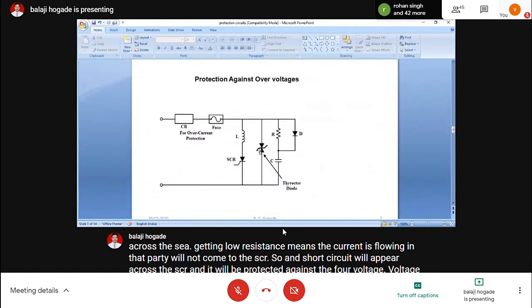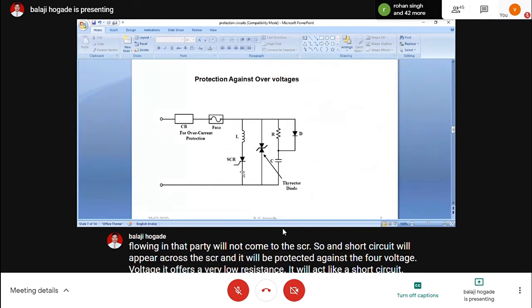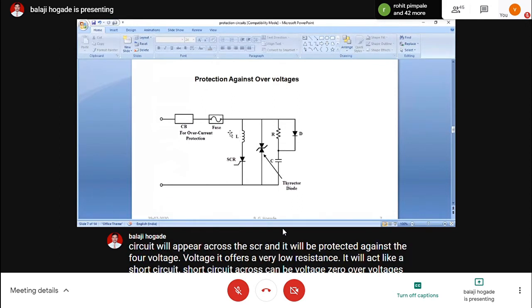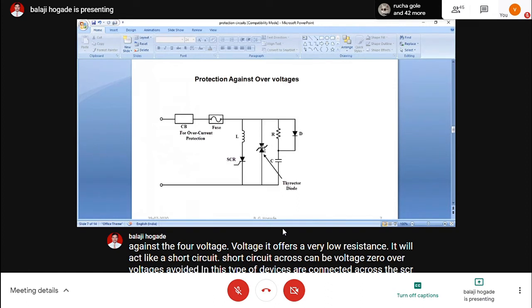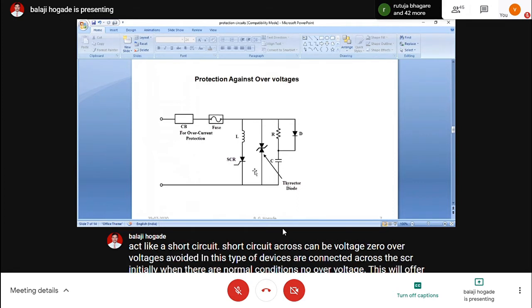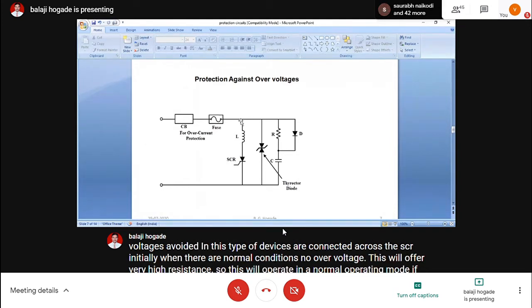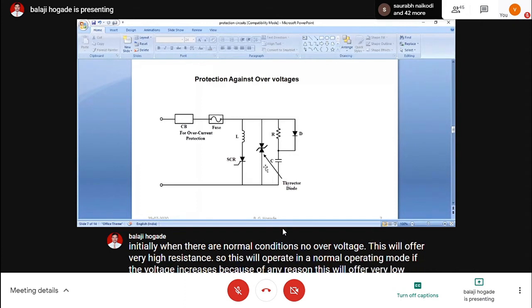This type of device is connected across the SCR. Initially, under normal conditions with no over voltage, it offers very high resistance, so it operates in a normal operating mode. If the voltage increases for any reason, it offers very low resistance, so the current which was flowing through the SCR path now flows through this path instead, creating a short circuit — meaning the voltage becomes zero.